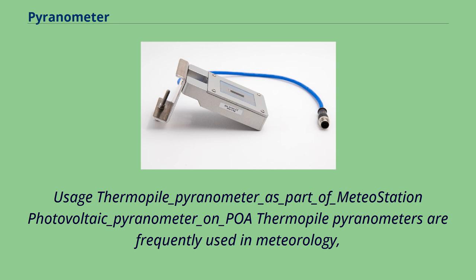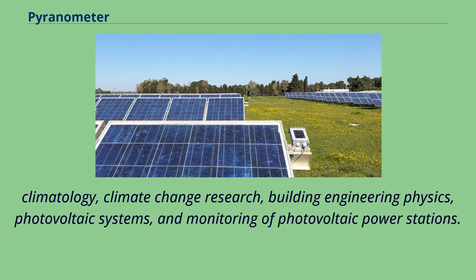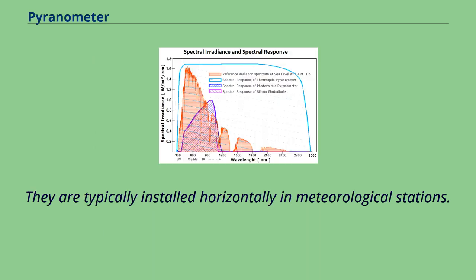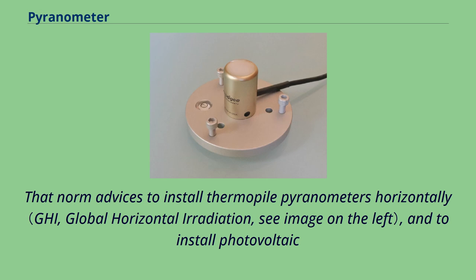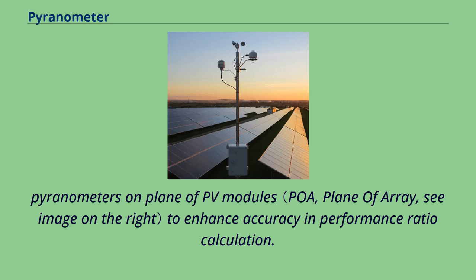Thermopile pyranometers are frequently used in meteorology, climatology, climate change research, building engineering physics, photovoltaic systems, and monitoring of photovoltaic power stations. They are typically installed horizontally in meteorological stations. The solar energy industry standard IEC 61724-1-2017 has defined what type of pyranometer should be used depending on the size and category of solar power plant, advising to install thermopile pyranometers horizontally and photovoltaic pyranometers on the plane of PV modules to enhance accuracy in performance ratio calculation.